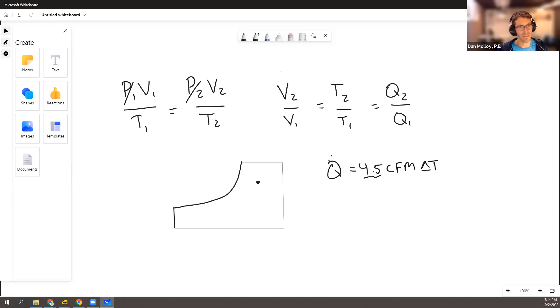And the assumption that's baked into this 4.5 constant, and it's the same for 1.08 CFM delta T if you're doing sensible only, is that the density is 0.075 pounds per cubic foot.